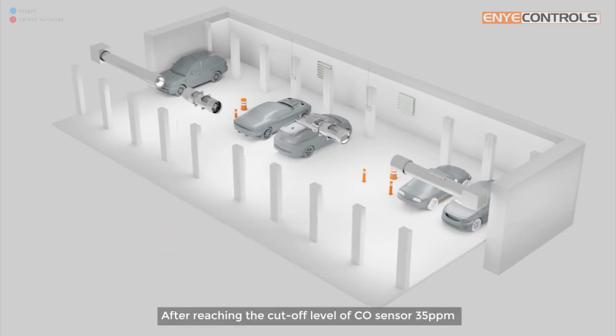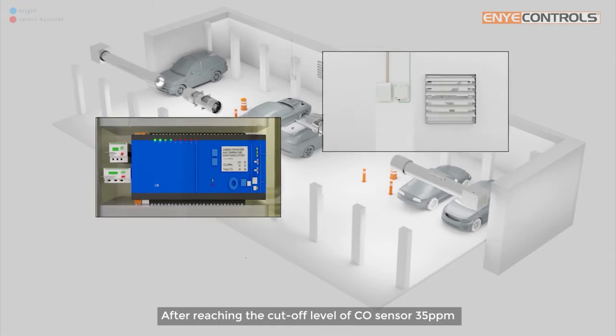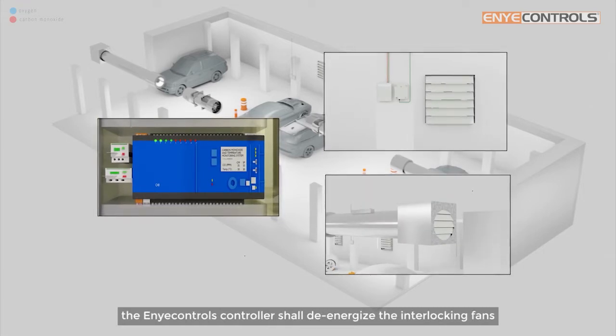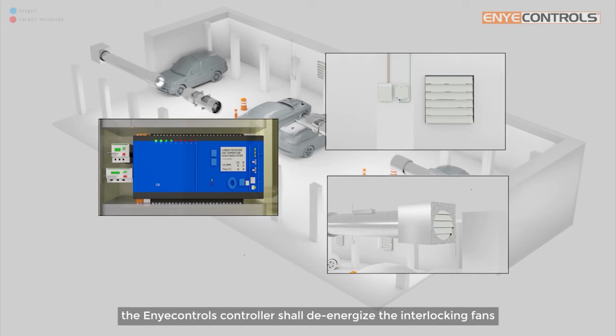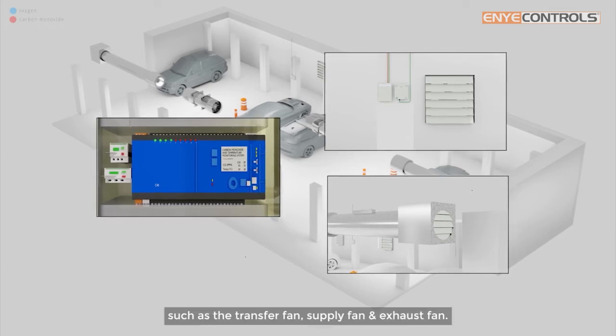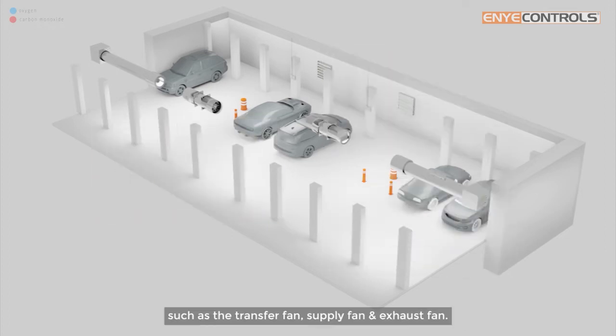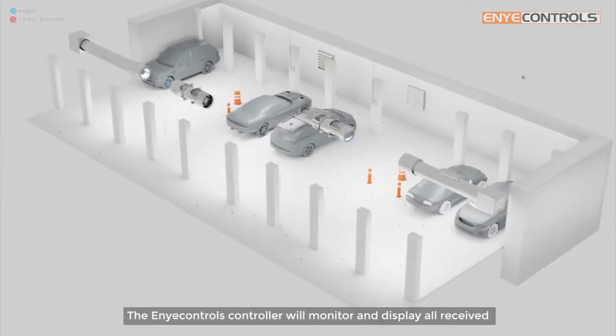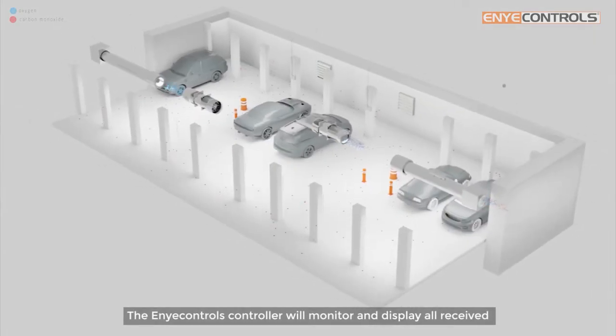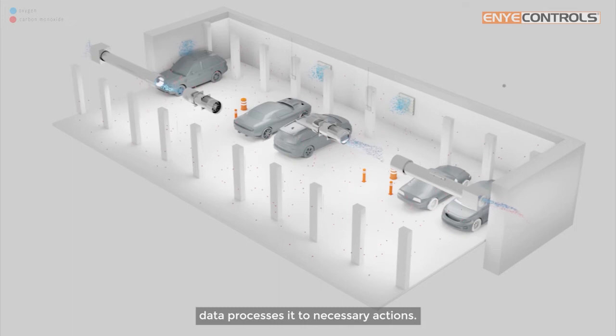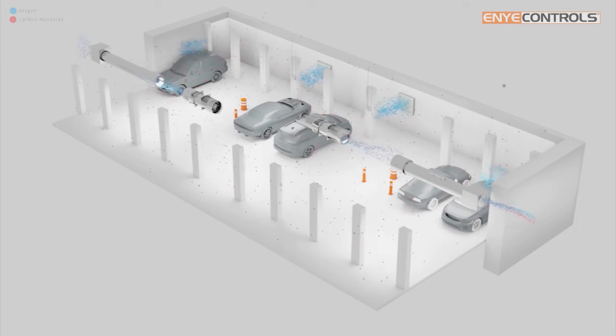After reaching the cutoff level of the carbon monoxide sensor, 35 parts per million, the Enyecontrols controller shall de-energize the interlocking fans such as the transfer fan, supply fan and exhaust fan. The Enyecontrols controller will monitor and display all received data and process it into necessary actions.